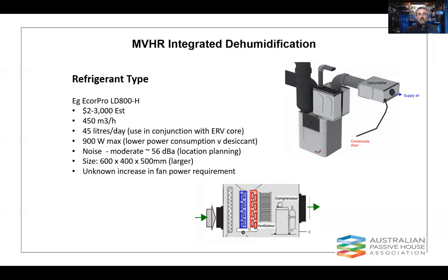They're a bit larger in size. Obviously, the compressor's got to be in there, a couple of sets of coils. There's a little more going on. There's some refrigerant being pumped around. And you'd want to check your standby coil pressure drop. So how much fan power, MVHR fan power, are you going to consume running across those two coils if you have it as a permanently inline device rather than in a bypass or a dog leg type arrangement.